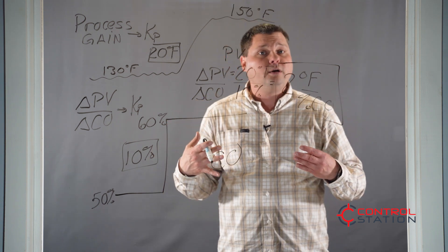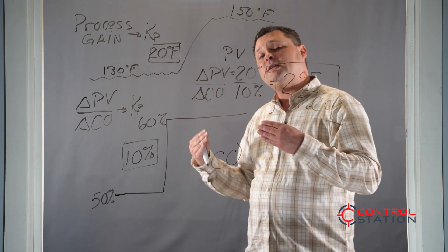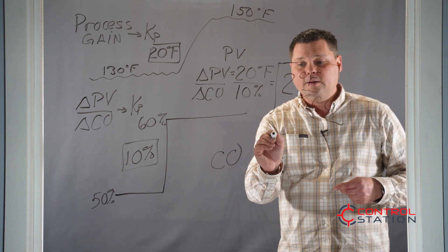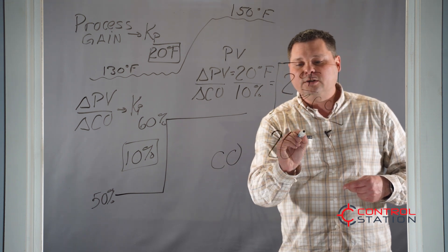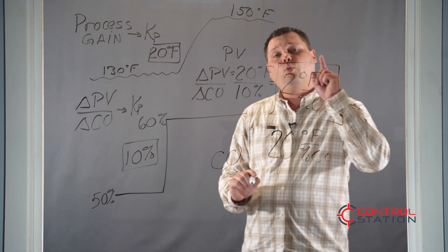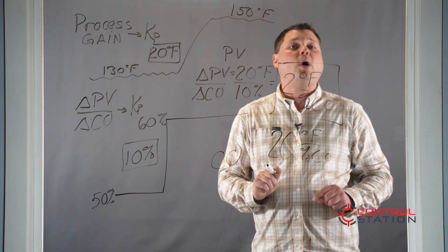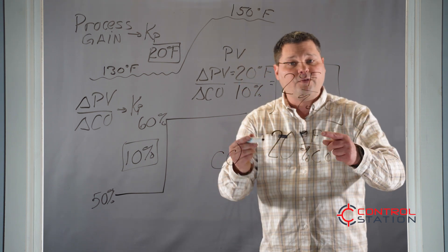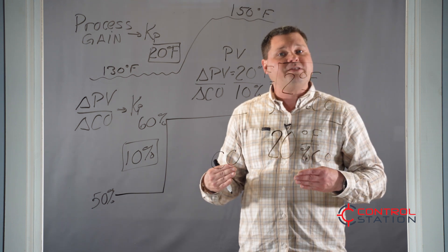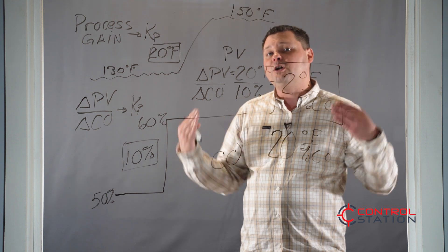The larger the number, the more sensitive the process variable is to changes in the output. If my process gain was not 2 degrees Fahrenheit but instead 20 degrees Fahrenheit per percent CO, that would mean for every 1 percent I move the control valve the temperature increases by 20 degrees Fahrenheit — obviously 10 times further. It defines the sensitivity of the process and gives us a lot of information about how well we can control it.